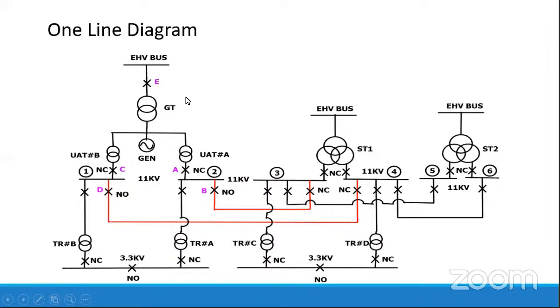So this is the single line diagram, and then the transformer steps down further and feeds another location at 3.3 kV, and then another outgoing will be there. Here you can see that at 11 kV the generator is generating power and feeding the two transformers, UAT A and UAT B, and the power from the grid is also feeding the network from the EHV bus. This power from EHV, meaning high voltage, with the help of this GT gets stepped down to 11 kV, and then it's further feeding another network.